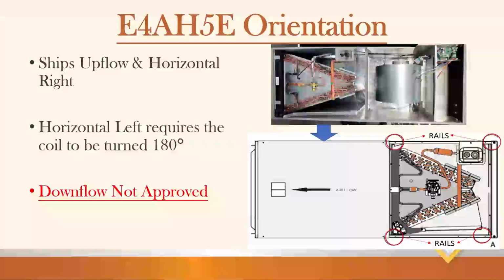Okay, ships upflow and horizontal right. Again, downflow not approved. We can't stress that enough. If you need horizontal left, it's not too bad, but you're going to pull all your screws. There's going to be rails up here that they're going to slide in. So you're going to pull that entire coil out, and you will rotate it 180 degrees and slide it back in.